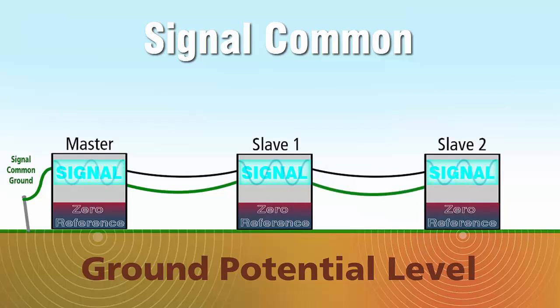The signal common ensures that each device will have the same zero-volt reference and will not inadvertently exceed the voltage limits of the hardware while transmitting data, because of potential level differences in the transmitter and receiver locations.